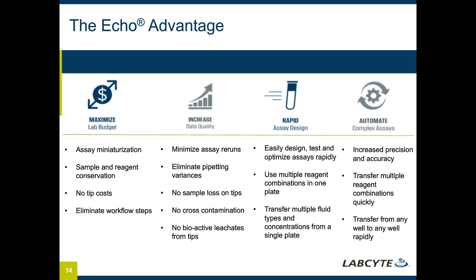There is certainly increased data quality. Even though they are miniaturizing their assays, very often the quality of the data exceeds what they were achieving before. We eliminate those pipetting variances through carryover from the tips. We don't lose sample on the tips, and I'll show you an example of how that might impact the type of research that you're doing. There's no potential for cross-reactivity. And of course, anytime you have plastics touching your sample, you're always opening yourselves up for bioactive leachates to enter that sample. And through the elimination of the tips, that's just one additional area that you eliminate there.